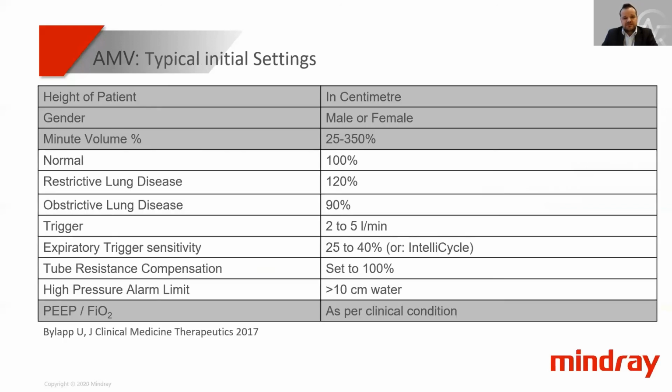In this table, you can see the initial settings of the AMV mode. Everything that is with the gray color needs to be adjusted by the physician. All the other parameters are done automatically by the algorithm.